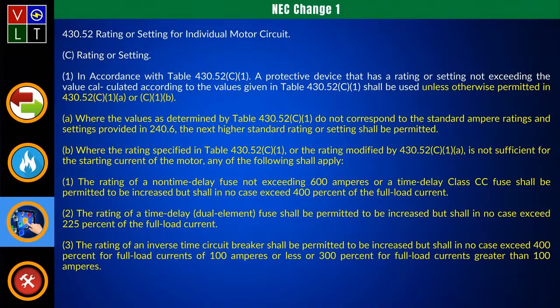Then if you look at (a), without doing any further calculation, I could go up to 175 amp. Now, if I look at (b), it even allows me to go up to what we call the maximum size at this point. And it says, if I have a full load current of 100 amps or less, and the motor was rated at 65 amps, I could take that at 400% per (b)(3) right there. So if I take 65 amps at 400%, that's 260 amps. It says I can't, once again, exceed that calculated load. So the next size below that would be a 250 amp.